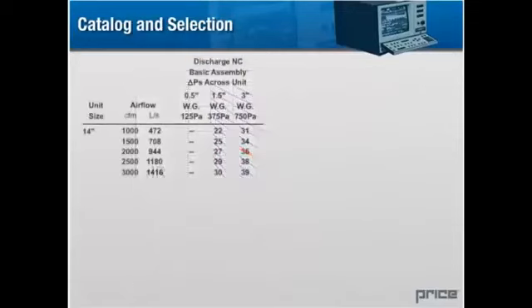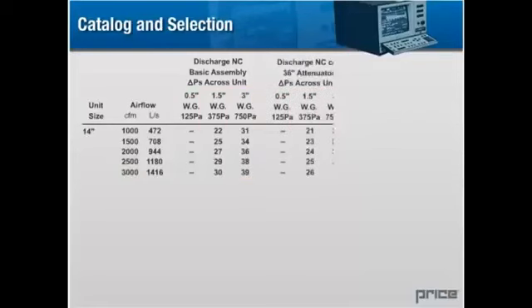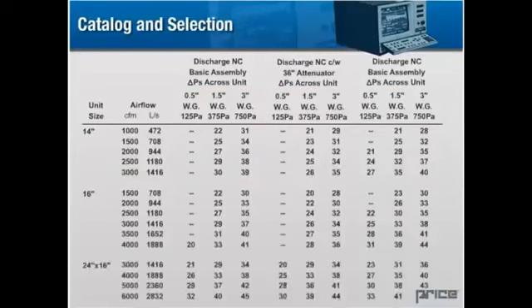Because we have sound power readings for various airflows and pressures, we can produce NC ratings that correspond to each of these combinations as well. This is a portion of a typical chart found in the Price catalog, which shows NC levels for a terminal unit under various conditions. Dashes are shown for circumstances where the NC level is less than 20, since the noise contribution would be so quiet as to be imperceptible in most settings. These figures appear in the catalog in typical selection guides for terminal units. Similar data appears as performance data for GRDs.